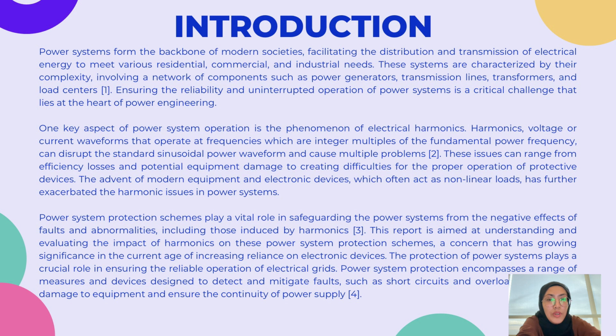Harmonic voltage or current waveforms operate at frequencies which are integer multiples of the fundamental power frequency, and can disrupt the standard sinusoidal power waveform and cause multiple problems. This issue can range from efficiency losses and potential equipment damage to creating difficulty for the proper operation of protective devices. Power system protection schemes are important because they protect against faults and abnormalities, including those induced by harmonics. This report aims to understand and evaluate the impact of harmonics on power system protection schemes.